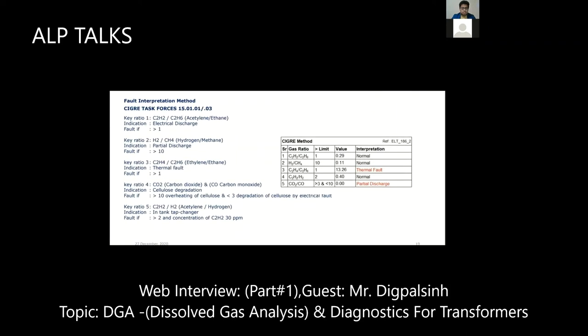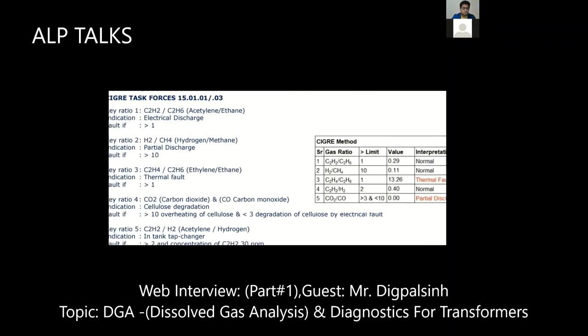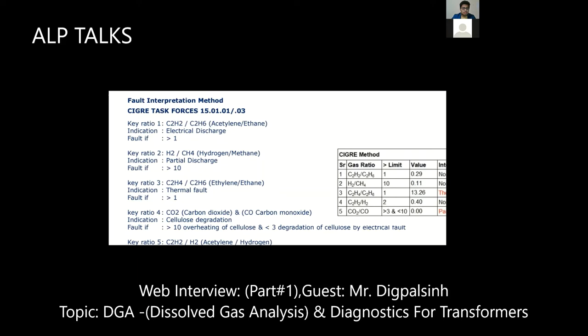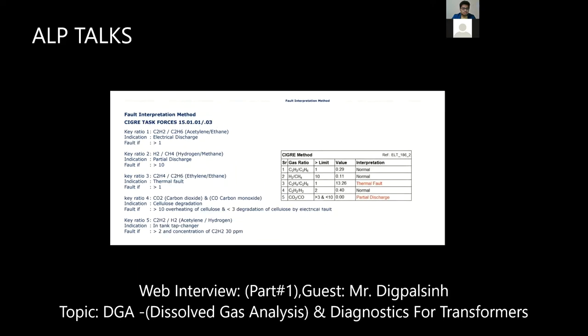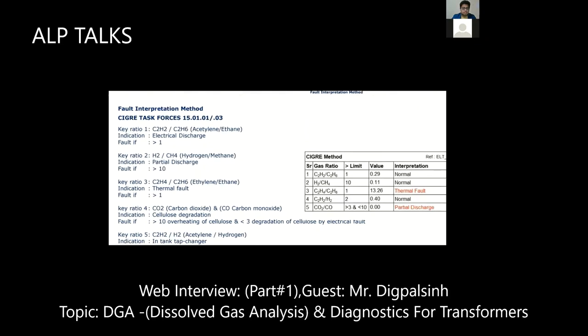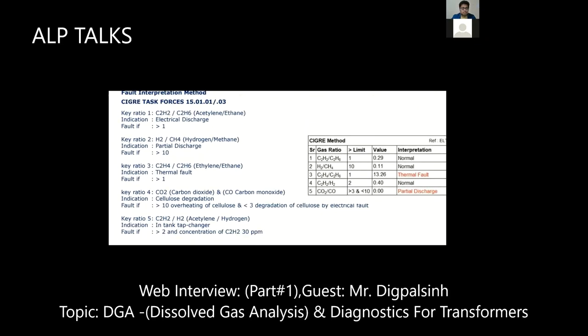Now CIGRE. Earlier you mentioned the task force TF 15.01.01. Actually CIGRE first invented this ratio method, and IEC has copied it. CIGRE has defined five key ratios. The first is acetylene to ethane. If this value is greater than one, then there is electrical discharge. Then you have to categorize it as D1 or D2, low energy and high energy discharge, or partial discharge.